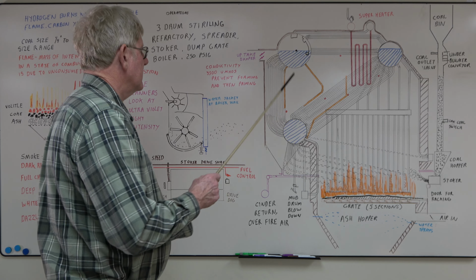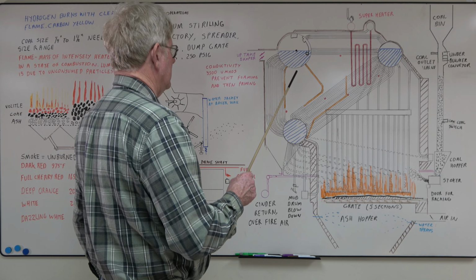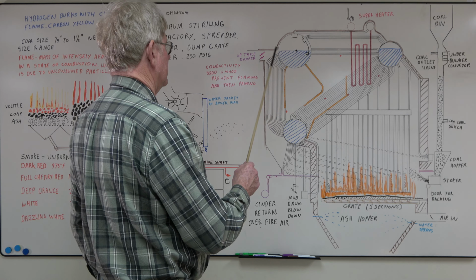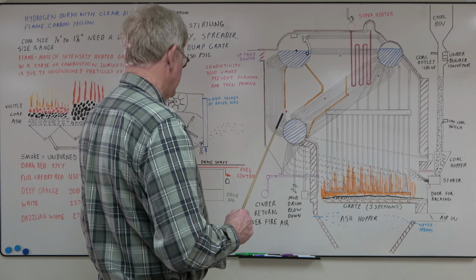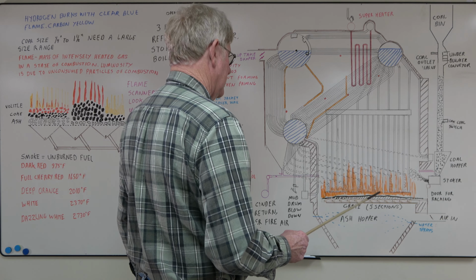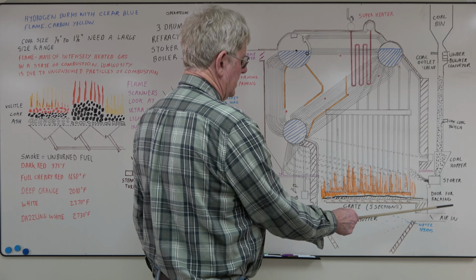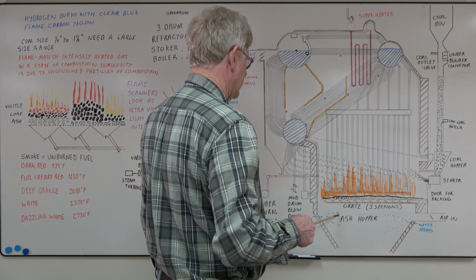On your boiler, if you ever had this thing out of water and put water in it, it'd probably explode because your safeties can't deal with all the steam that'd be generated. The big thing to run in these was to maintain a uniform fire bed. Control your air. You had an FD fan, steam turbine. You'd adjust the steam flow to that to control the airflow coming in.